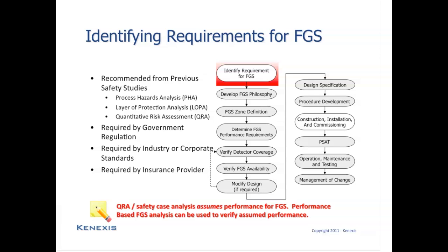So if a quantitative risk analysis has been performed for your facility and it was the basis to go to a regulator to get an operational permit, then the actual facility needs to have a fire and gas system in place whose performance is in accordance with the assumptions that were made during that quantitative risk assessment study. In a lot of cases, fire and gas system implementation is going to be required by government regulation. A lot of regulators will specifically stipulate that if you want to operate a certain type of facility, such as perhaps a liquefied petroleum gas storage facility, they're going to require that you implement some degree of fire and gas detection and suppression systems.